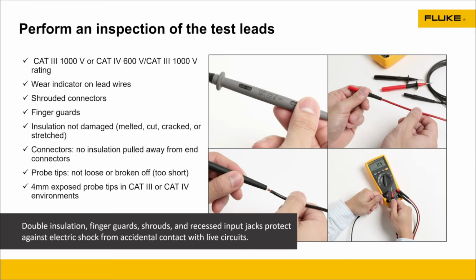Make sure that nothing's damaged, the test leads are working correctly, the finger guards are there, and there's no insulation damage. One of the key ones is your test probe. Look at the ends of it. Make sure that they're not broken or arced. I've seen it. That arc happens and you've got a jagged edge on that probe.